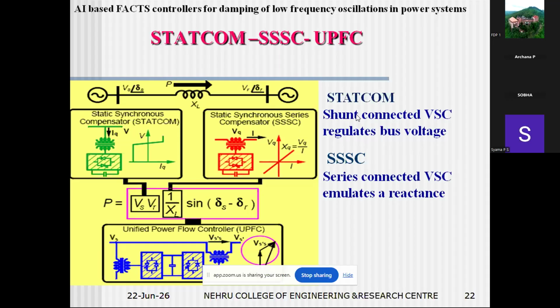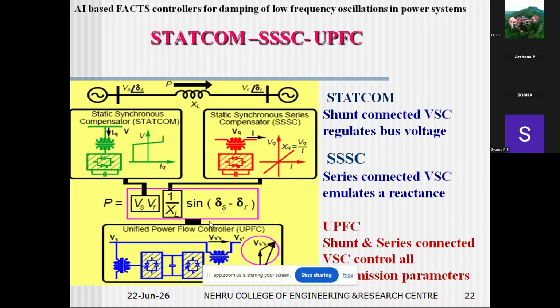And finally, if you have something called a unified power flow controller, the advantage is you can control all of these parameters. UPFC is a combination of shunt and series converters. You have a shunt converter and a series converter. Using this technology, each can do its own reactive compensation, and real power can also be compensated. If real power is taken from one side, it can flow through the DC link and be compensated by the other device, since this cannot generate real power. So whatever real power compensation is done, it is compensated by the other device.